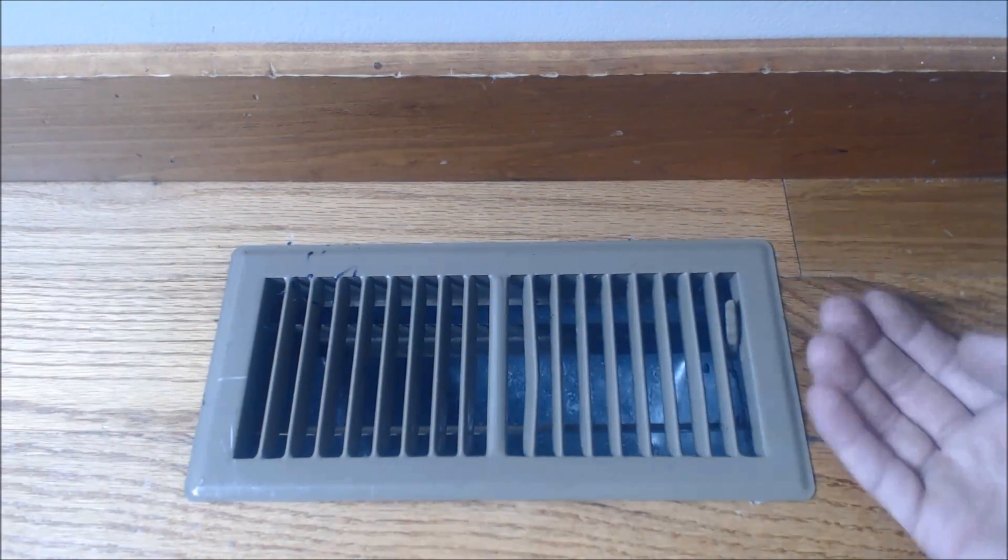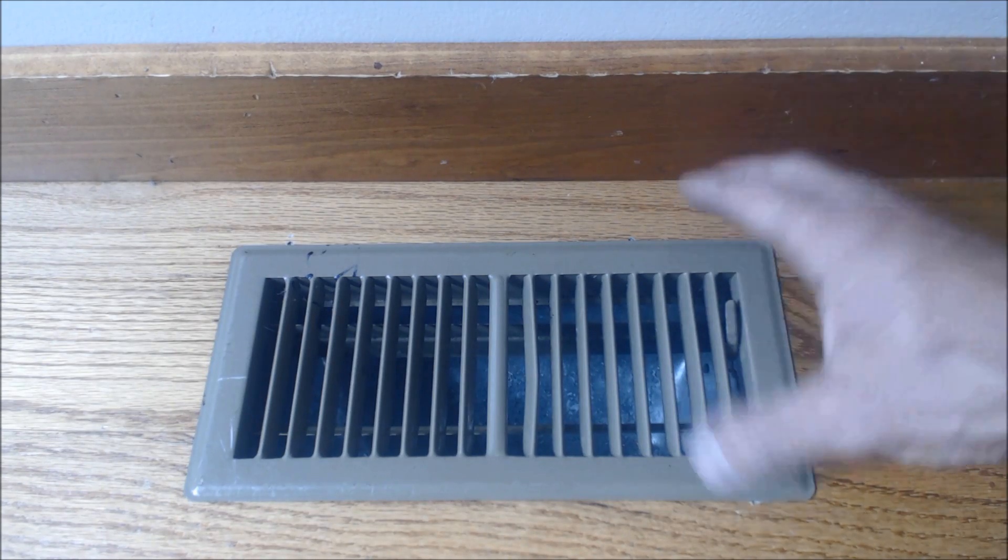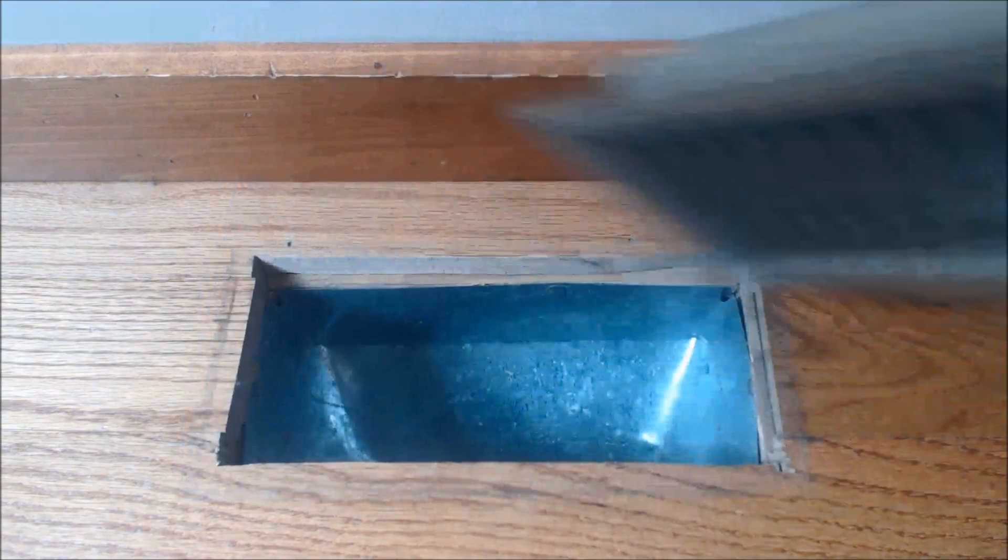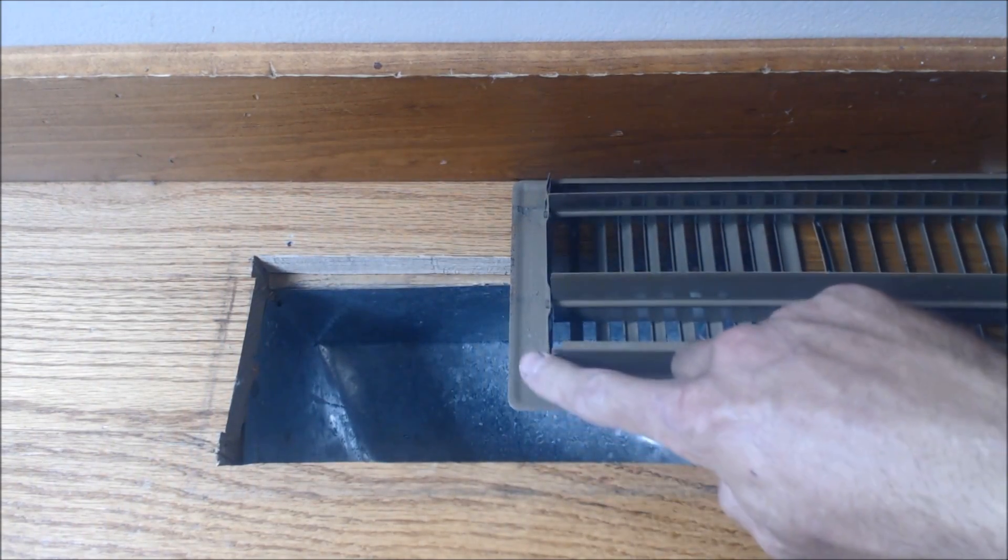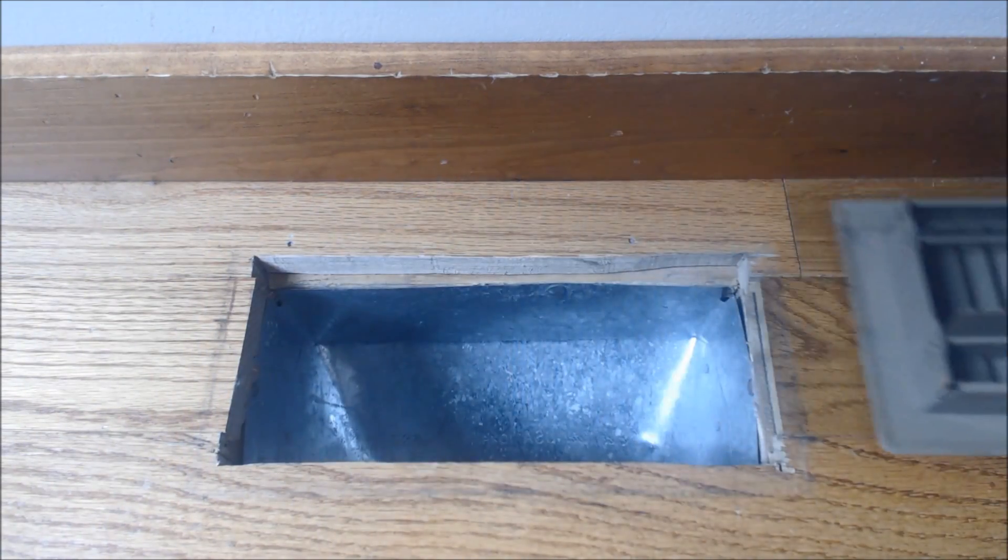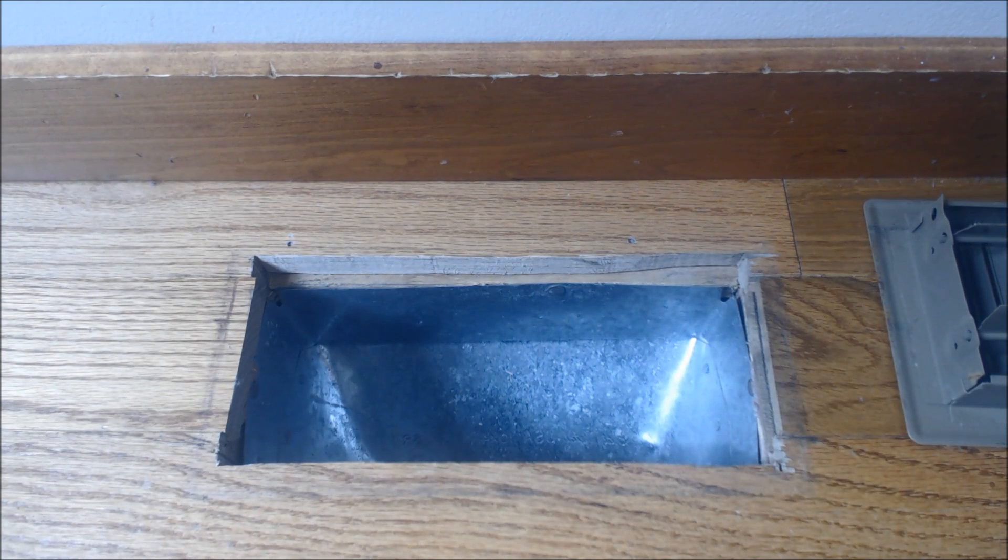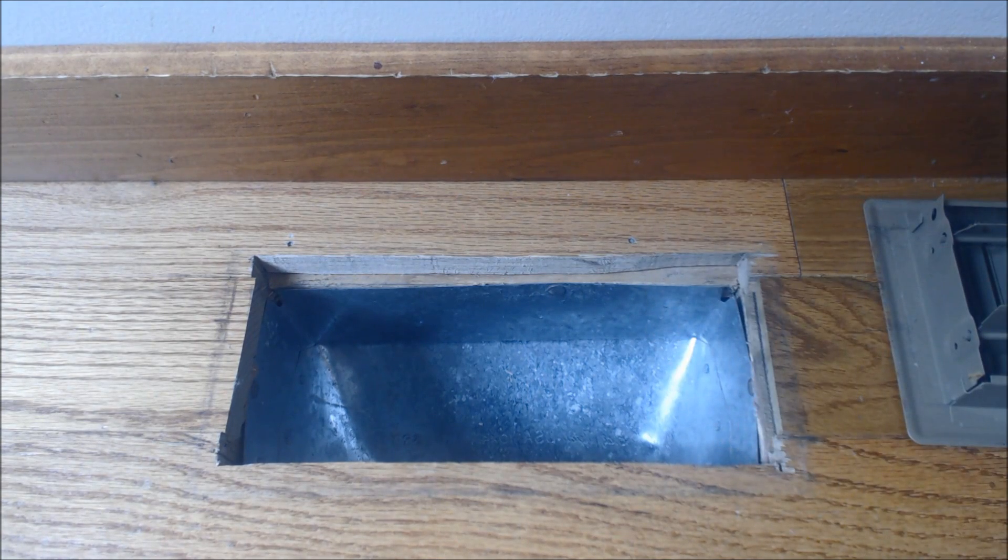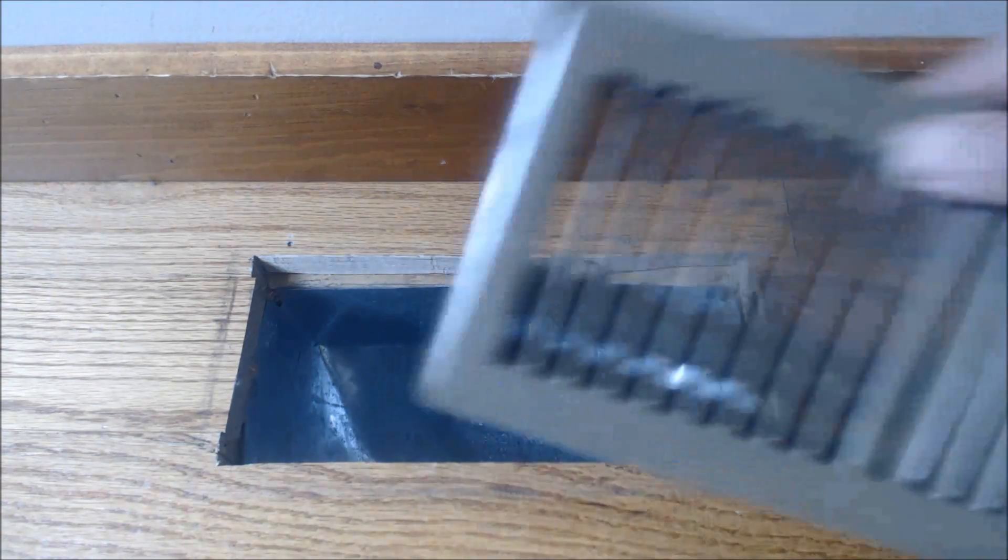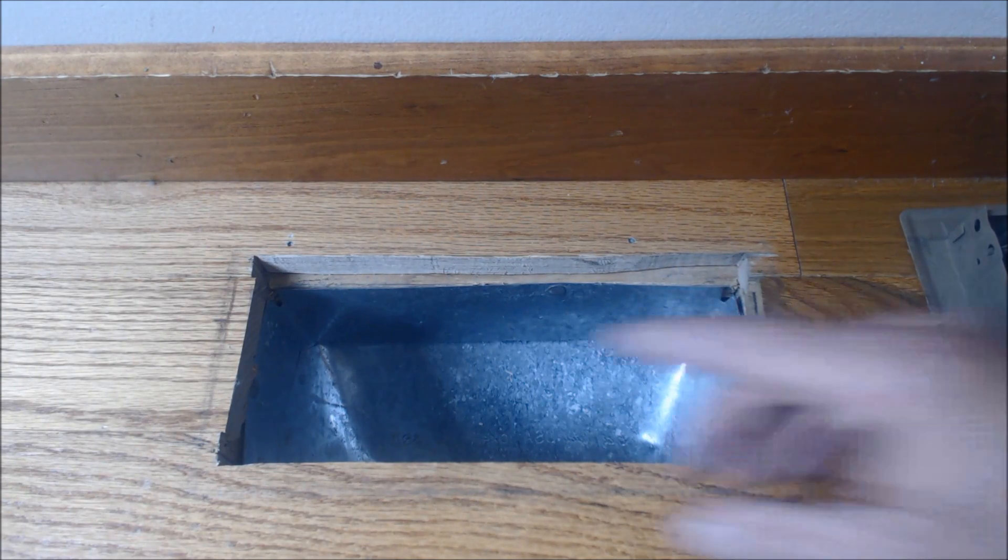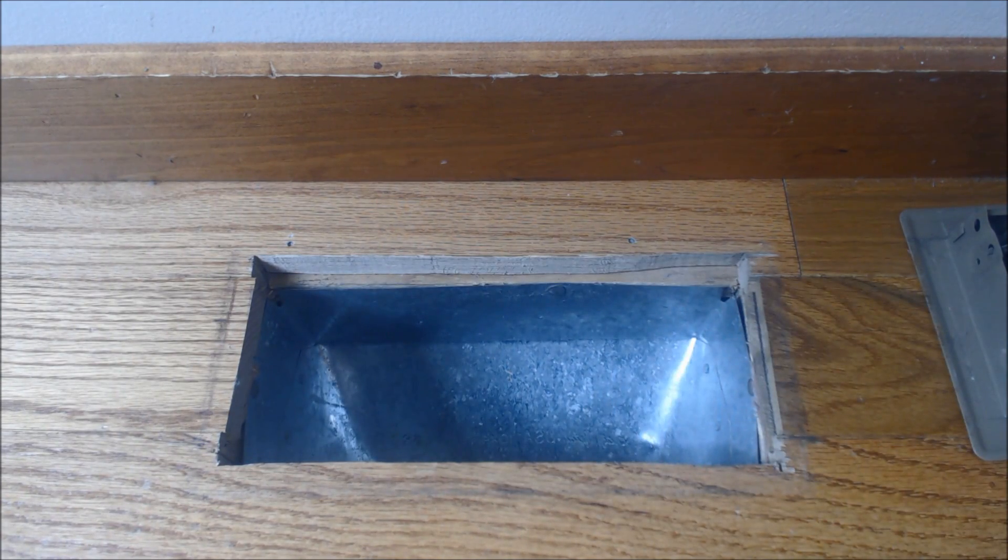For instance, air pushing up from the supply register could find its way behind the register and back down the hole, which means your house goes into negative pressure. It has to make up that pressure somewhere by stealing air from outside. The air goes with the path of least resistance. So you want to seal this up, and we're going to do that right now.